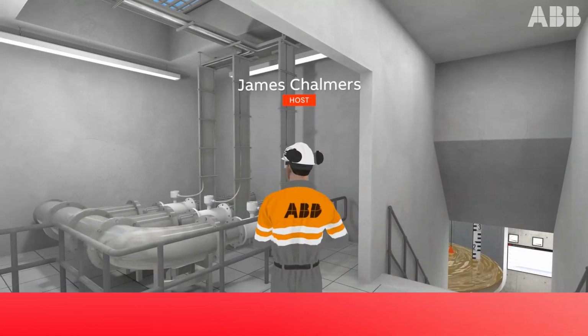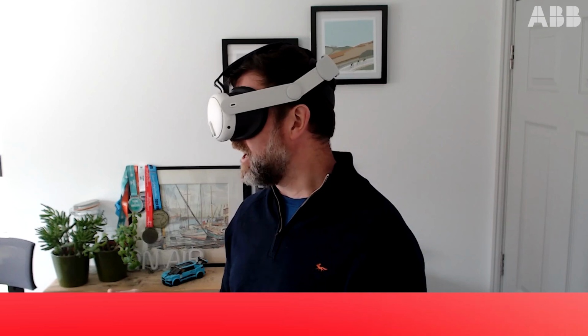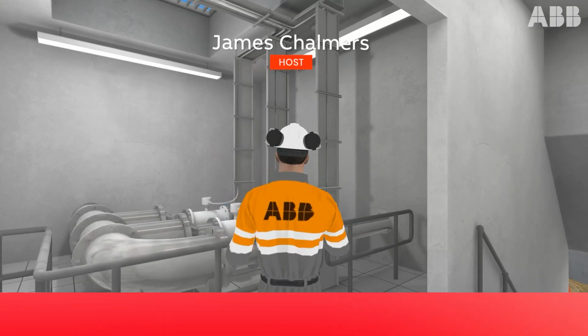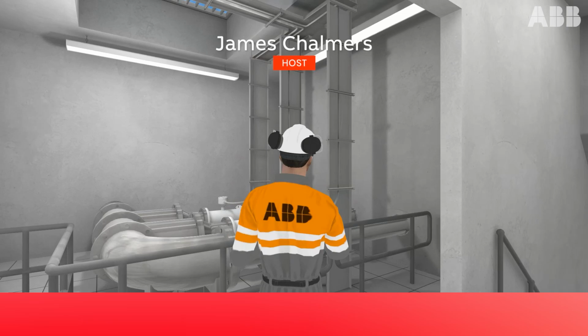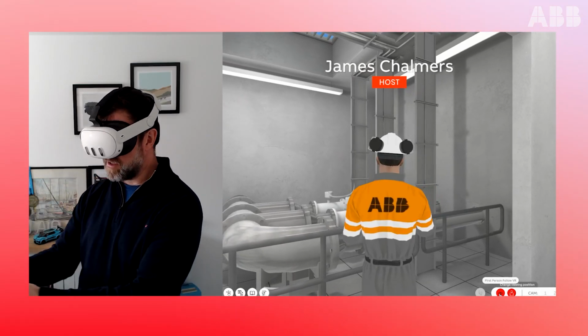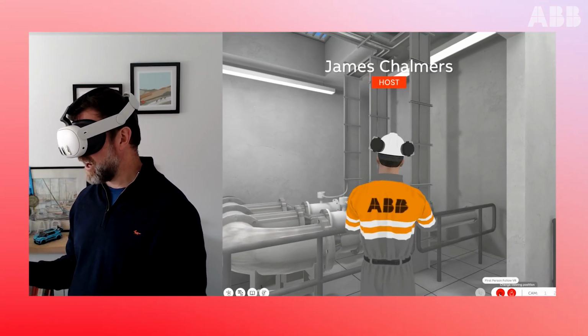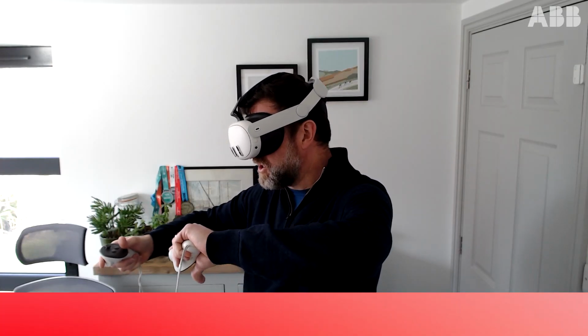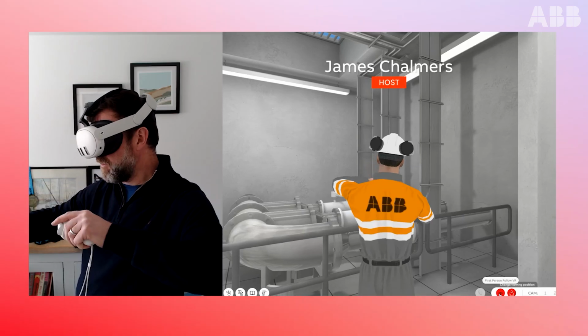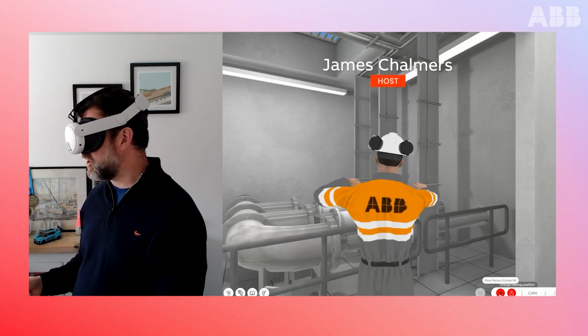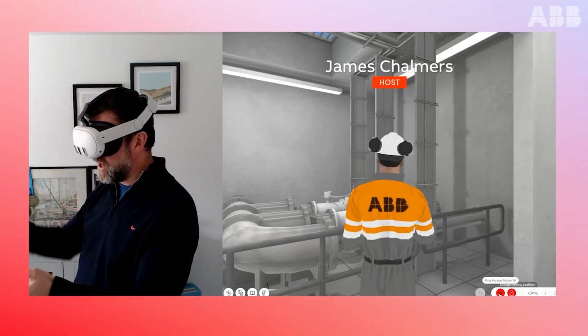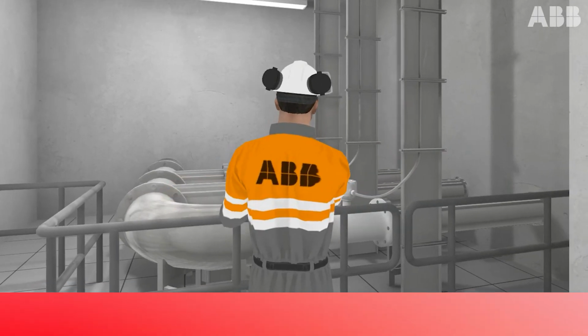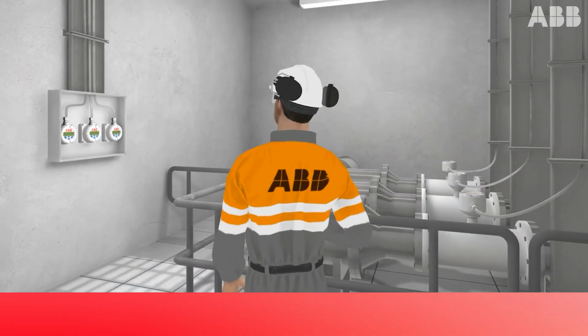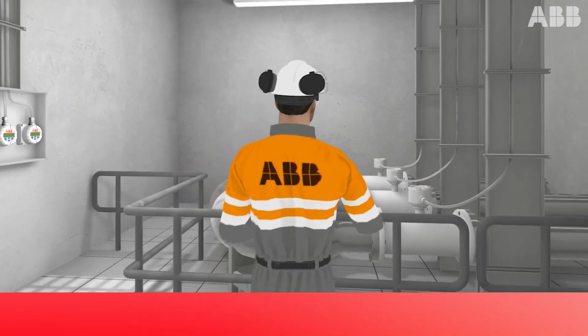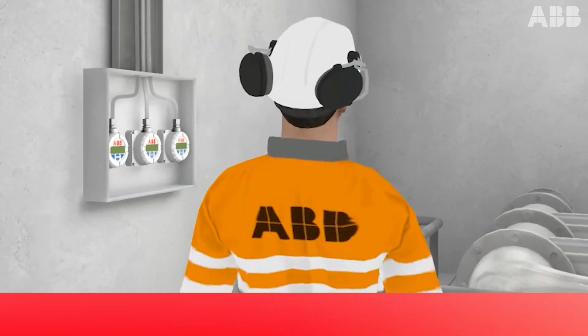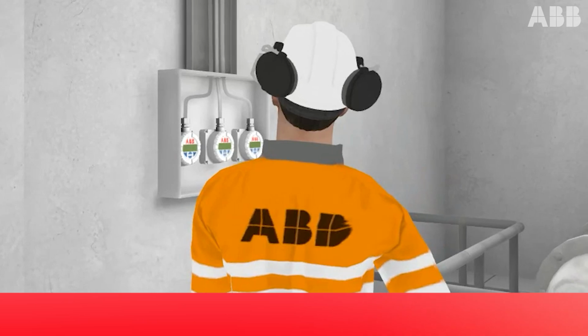Halfway down, these are the flow meters. And for those of you with a really keen eye, you'll see one of the big selling features of the flow meter is the fact that it doesn't need massive amounts of straights before and after the flow meter to get the accuracy. The design of the flow meter internally allows the vortex to be correct, so that we can have a high level of accuracy without massive lengths of straight pipe before and after. And you can see in this case, to avoid you having to clamber over to pipe number 3 to read it, we've used the remote keypads. Another feature of the flow meters.